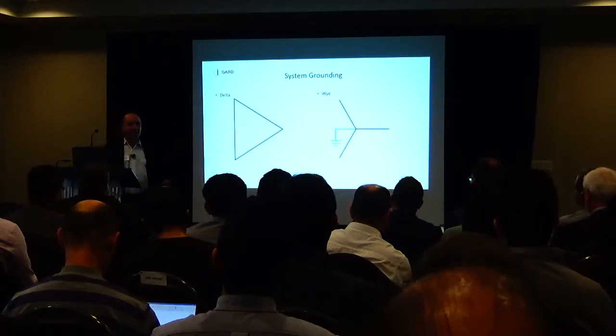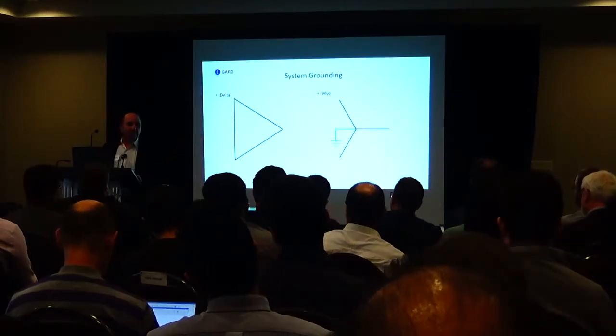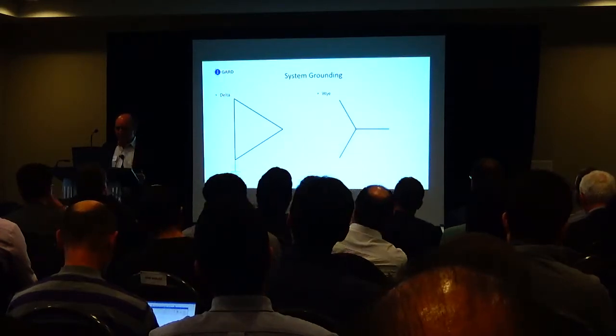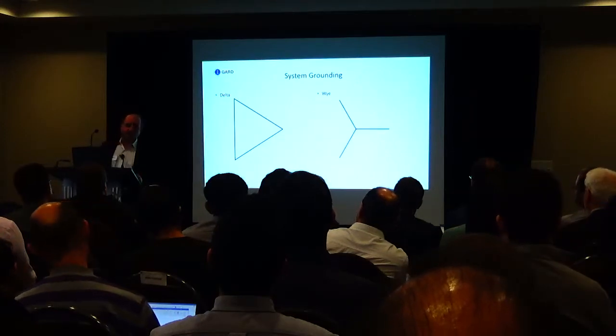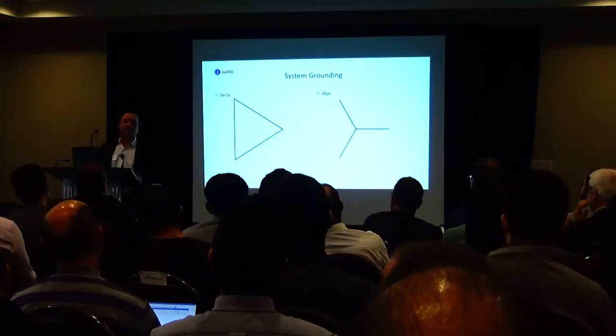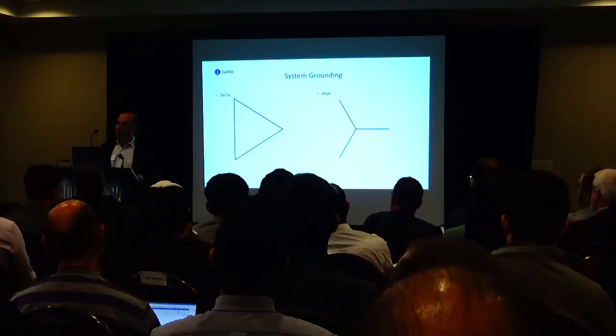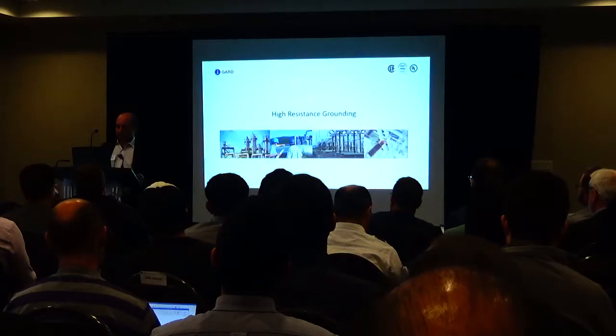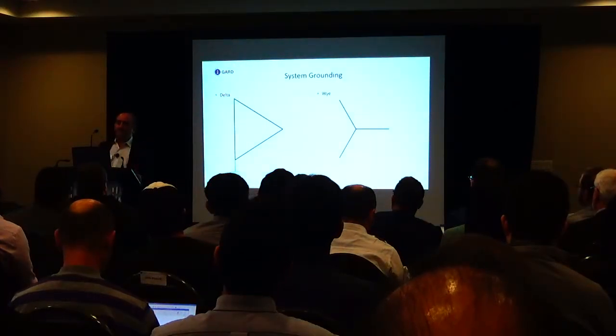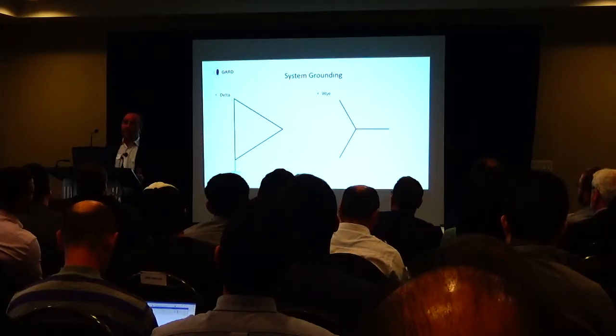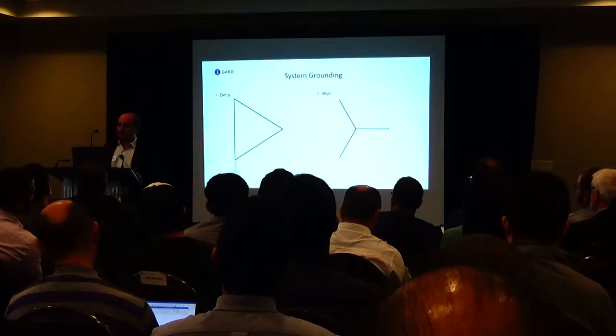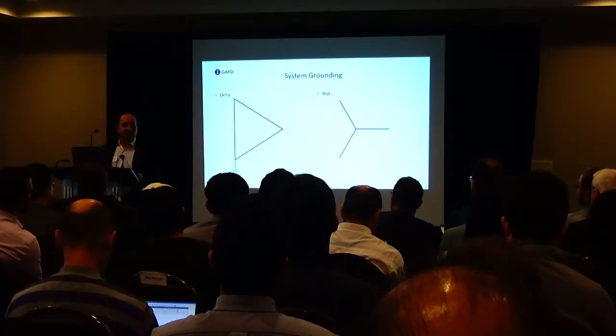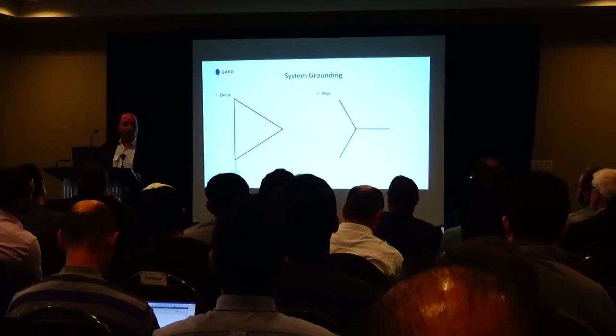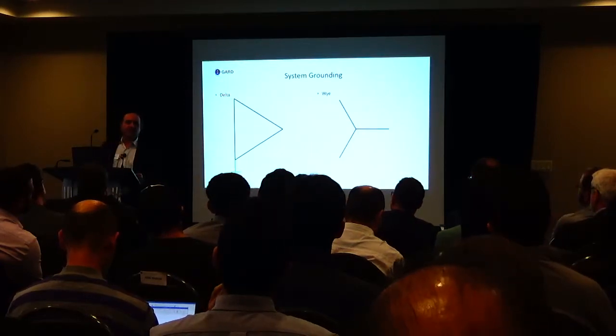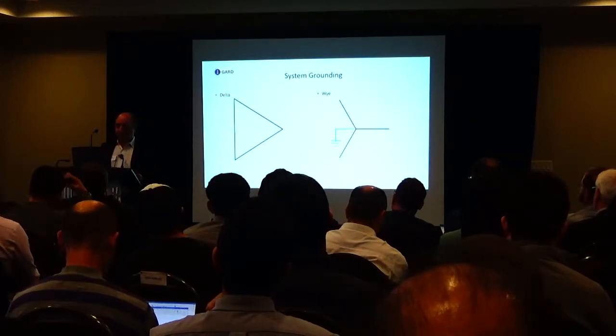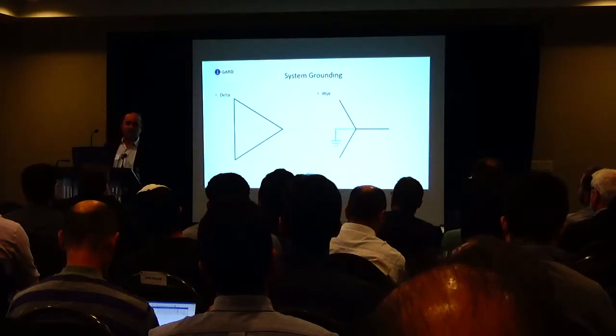So, in a Y system, we have the same thing. Take the neutral point and connect it to ground. So let's go back. Ungrounded systems. The Canadian Electrical Code says for ungrounded systems, you must have ground fault detection. There is no ground fault protection, only detection. Solidly grounded system, the code says if you have a system that's greater than 150 volts to ground and greater than 1,000 amps, you must have ground fault protection. Must. And you have to trip in less than 1 second for over 150 volts to ground or 2,000 amps at 208. This is a solid grounded system. This is another solid grounded system. This is the one where everyone's used to this one, right?